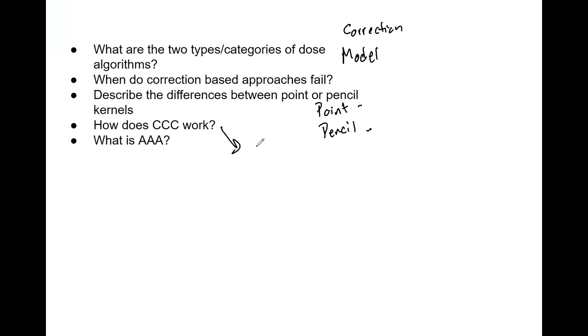Now it does use point kernels, so as we discussed before, those are highly accurate and those are radially symmetric cones—ultimately that's what it's determining and finding. But then it collapses that cone on itself, and so it has great accuracy, it's very fast.